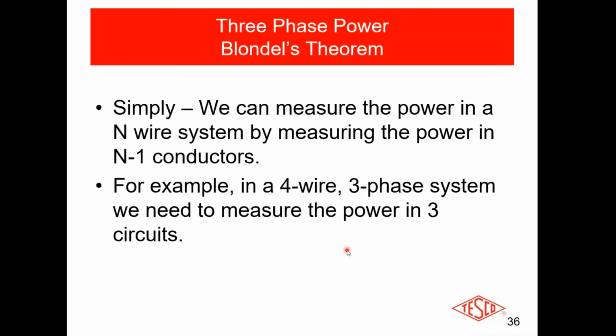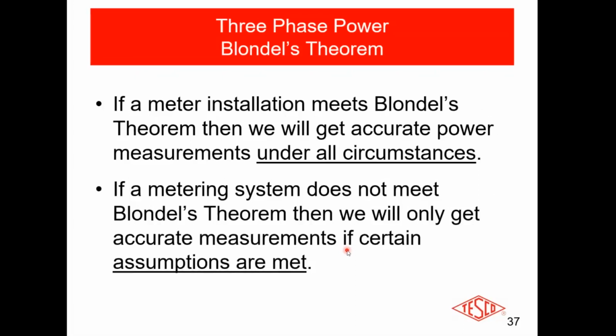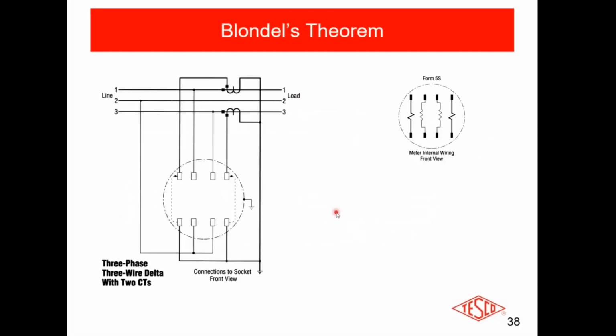A 12S meter, on the other hand, very similar meter, except it's got 2 watt meters in it, which means it is a Blondel compliant meter, and it can accurately measure energy in a 3 wire system. Okay? So if the meter installation meets Blondel's theorem, under all circumstances, you're going to get accurate power and energy measurements. If it doesn't, you're only going to get an accurate measurement if certain conditions are met. All right?